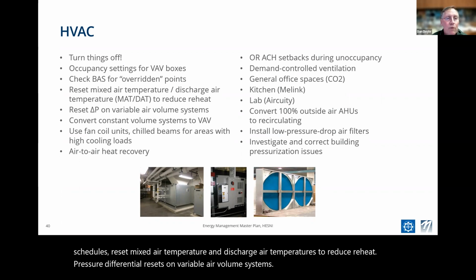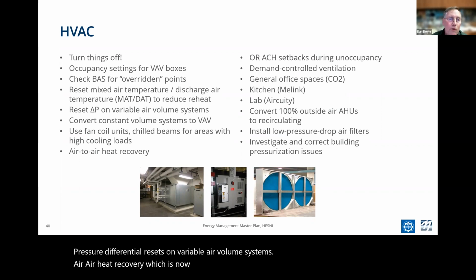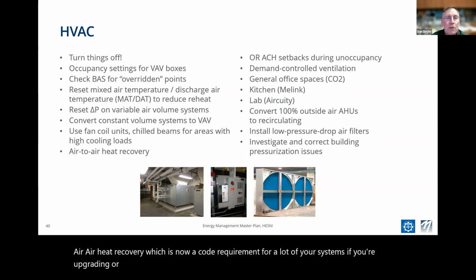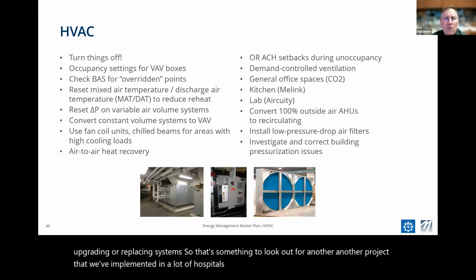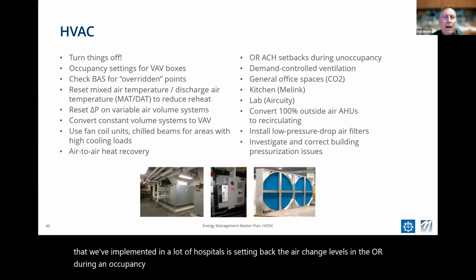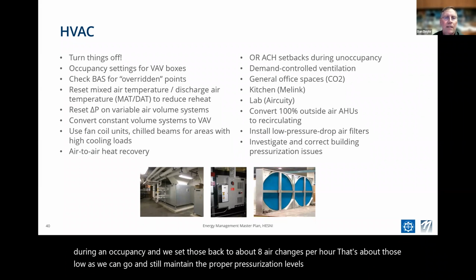Air-to-air heat recovery, which is now a code requirement for a lot of air systems if you're upgrading or replacing systems. So that's something to look out for. Another project that we've implemented in a lot of hospitals is setting back the air change levels in the ORs during non-occupancy. And we set those back to about 8 air changes per hour.